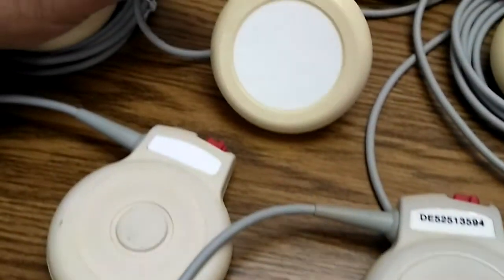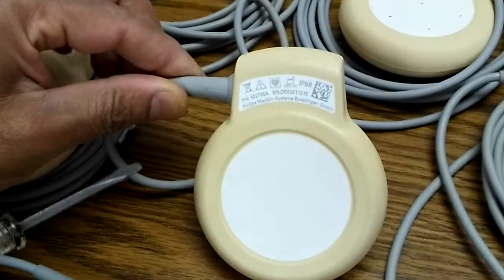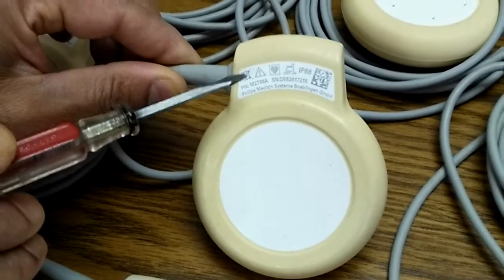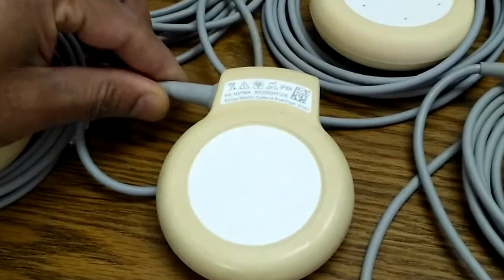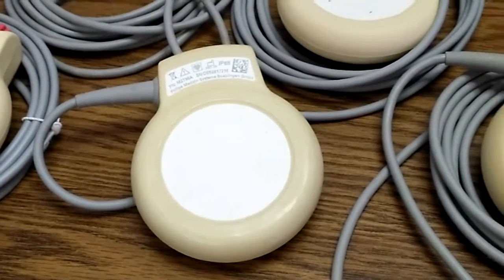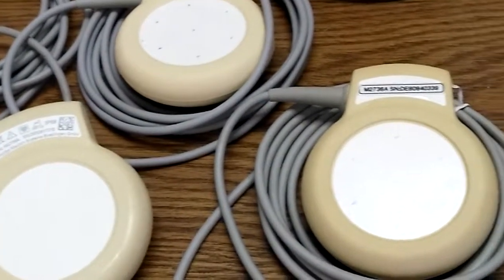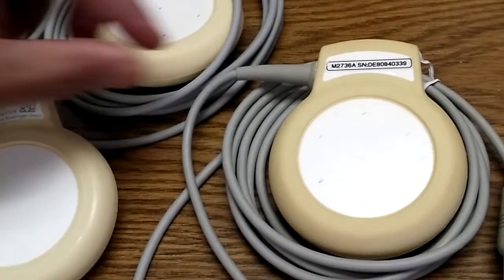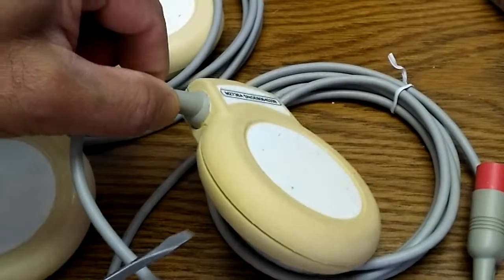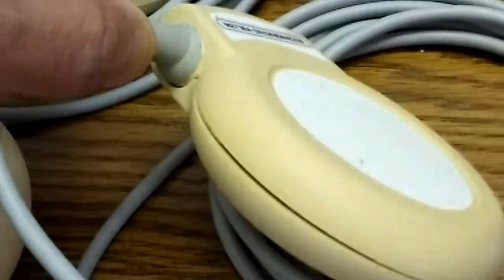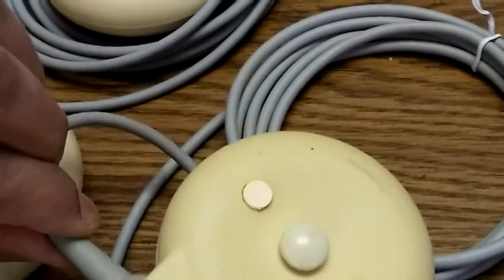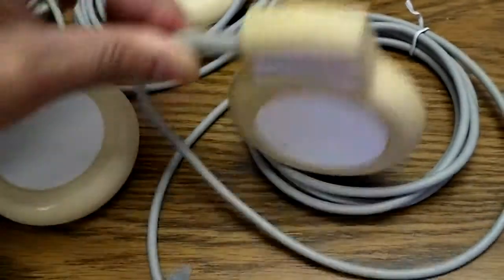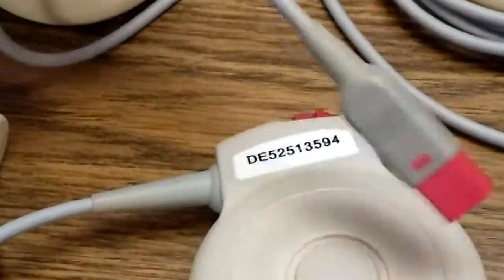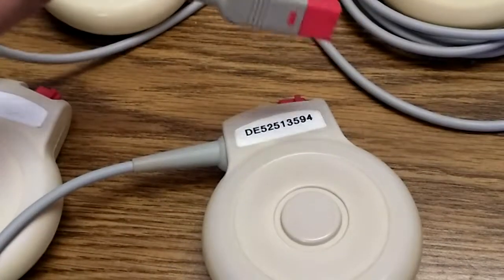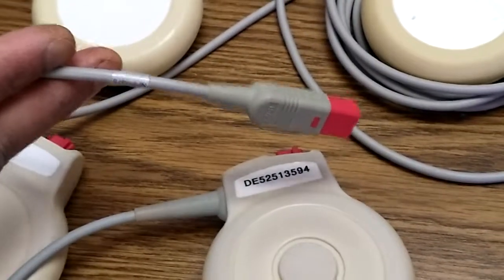There's a clear distinction. This is an ultrasound transducer, showing how the original plastic cases look and the Philips factory label. On the right is an ultrasound transducer repaired using non-Philips parts from the same hospital, and you can see the plastic cases have started coming off. The knob is crooked. The screw caps do not fit properly. The molded connector looks as if it is original, but there is a very clear distinction if we compare it with the brand new transducer.